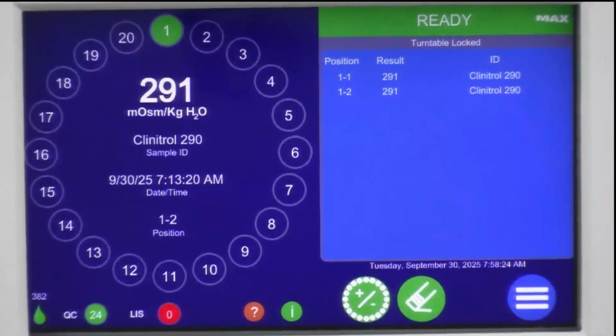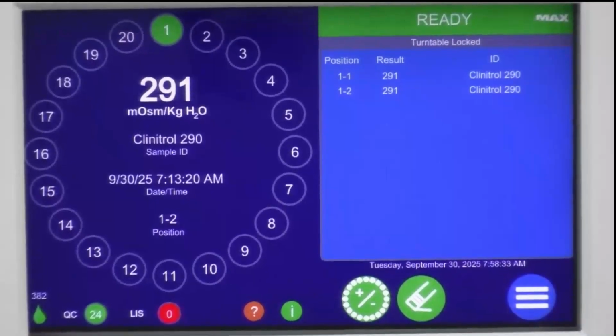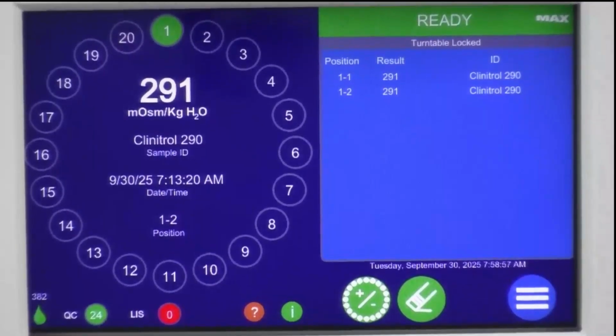Over here, the next symbol you're going to see is QC, and it says 24. So the QC on this instrument will lock out if it's not run every 24 hours. And when you install the instrument, you are going to designate a given time each day that this QC has to be run by. So once you run the QC, it will turn from red to green, like where it says red in that little LIS section over there. It will turn from red to green, and then it will also count down from 24, the amount of hours left until you have to run the QC again. So that makes it really helpful.